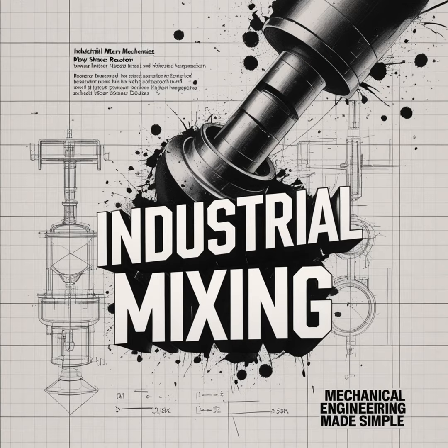So once that time, which we can call theta, is determined, engineers use the dimensionless mixing time, N theta. N theta is one of the key scaling parameters in mixing. It's the product of the measured mixing time, theta, and the impeller speed, N. It represents the total number of impeller revolutions required to achieve, say, a 95% state of uniformity. And if you can keep that dimensionless number constant as you scale up, you have a very solid basis for transferring the process to a larger vessel with a good chance of success.